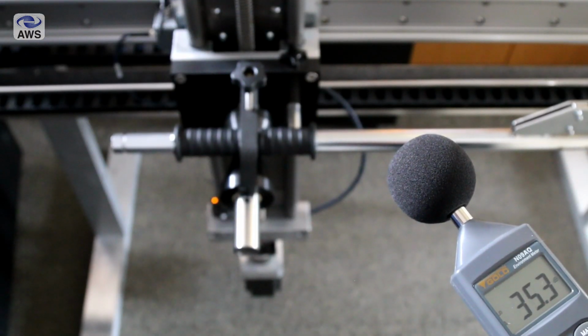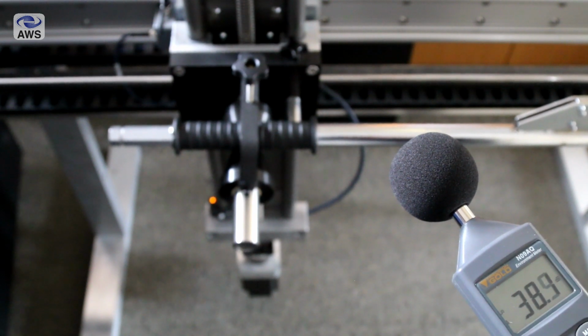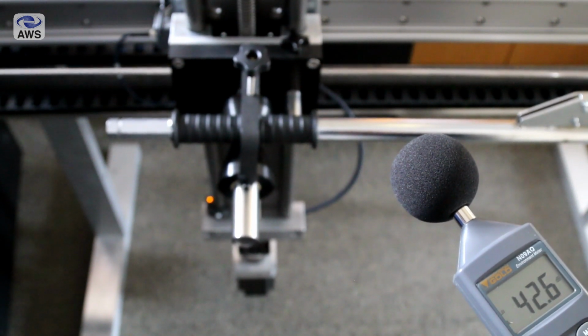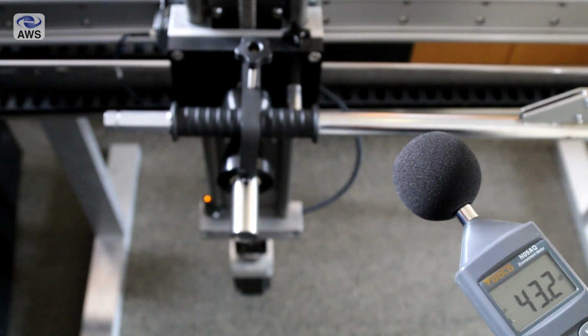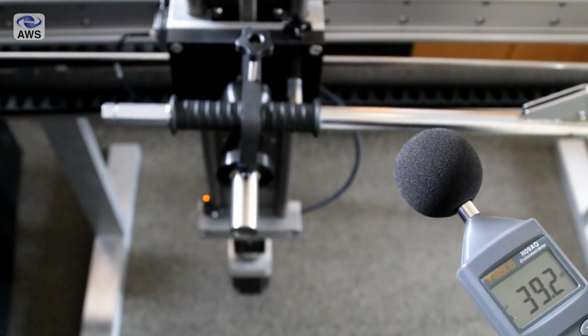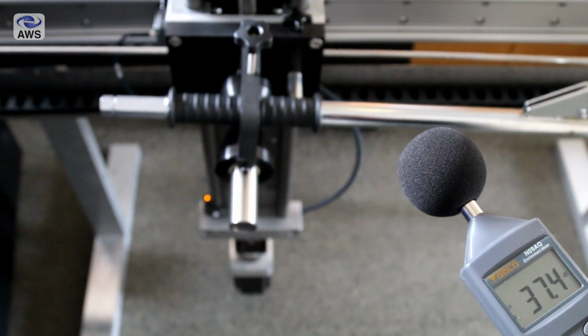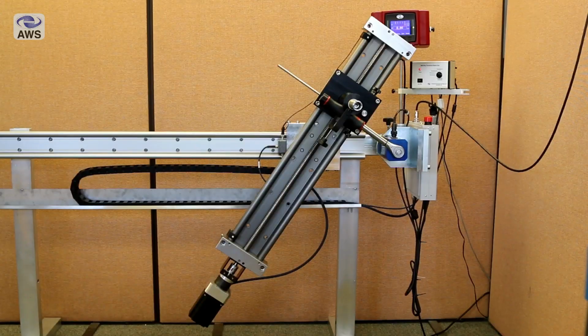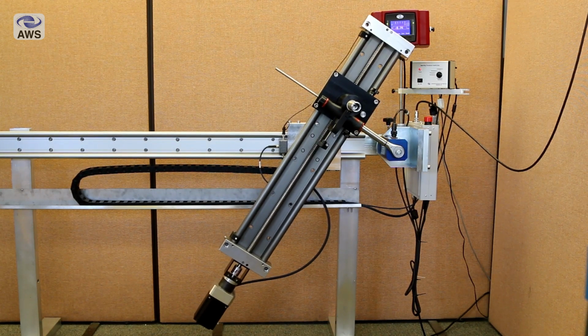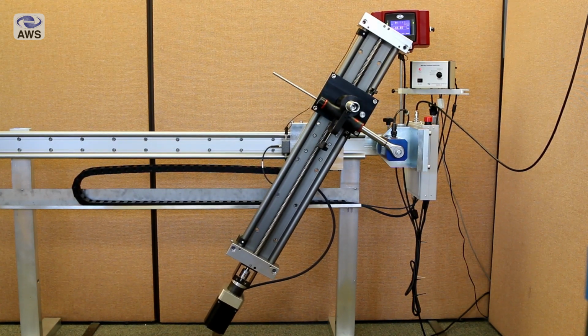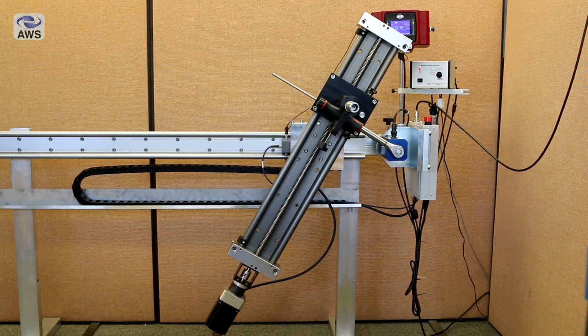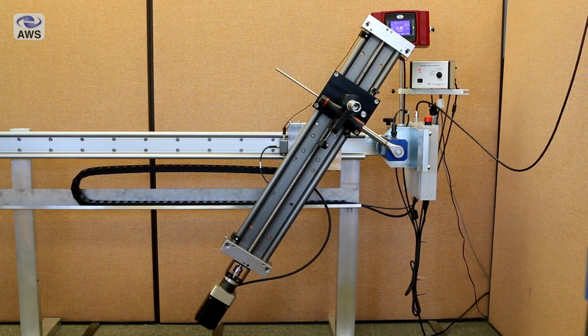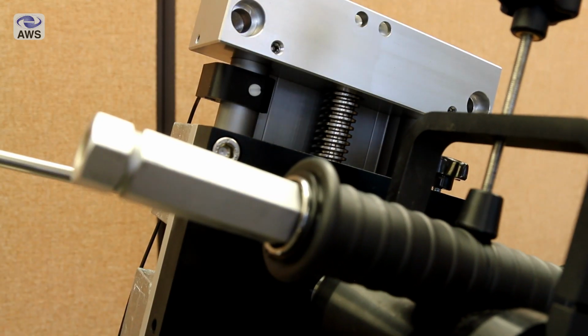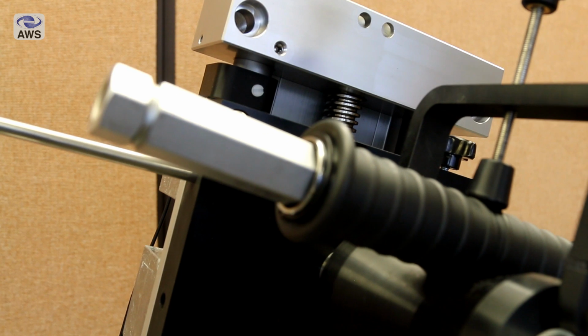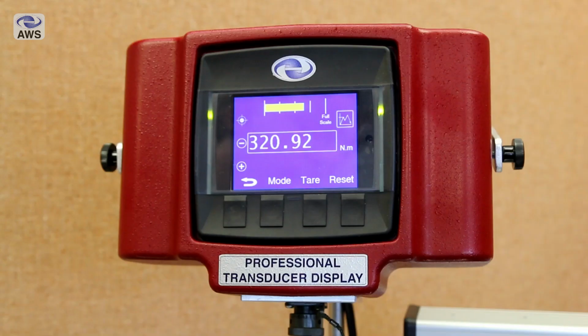The operation itself is both quiet and smooth. The long linear track ensures sufficient travel for cam-type wrenches. The calibration machine will increase speed from the peak detection, travelling quickly up to the wrench reset or click. This speeds up calibration time. There are multiple safety features to ensure that the machine, transducers and torque wrench are not overloaded in operation or overdriven due to wrench fault.